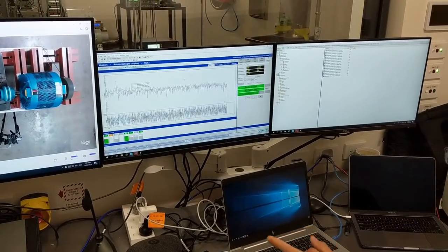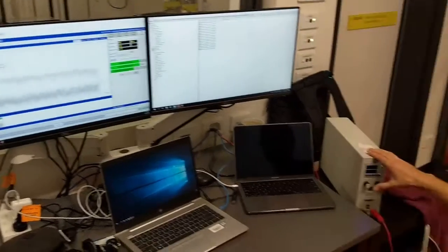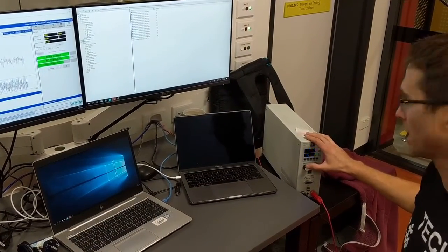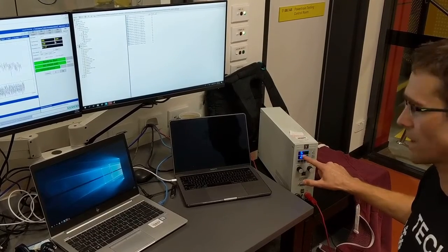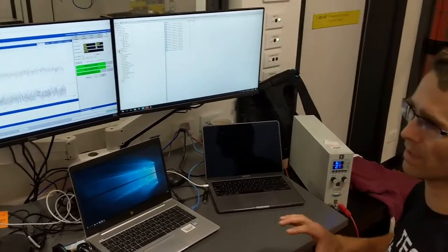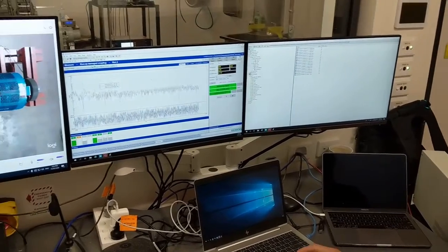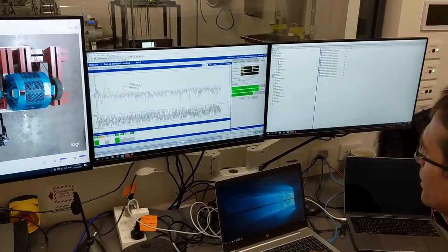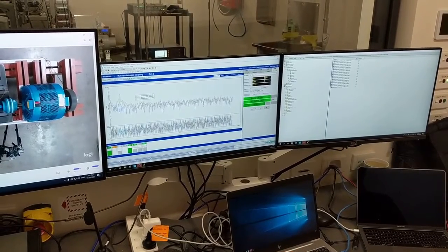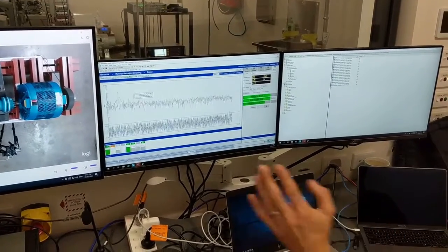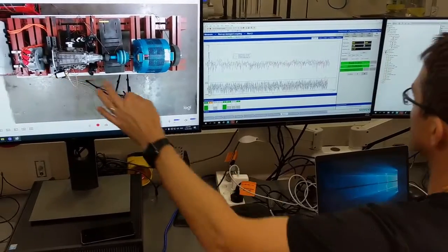We're about to begin a run-up test. We use this power supply here to set the voltage across the coils on the eddy current brake. So we're currently setting this to 6 volts, which will be about an intermediate load. And I'm going to arm the system. We're going to create this run-up, taking RPM increments between 200 and 1800 on the input side of the system.